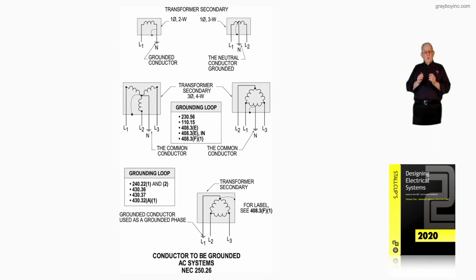I was very fortunate in one manner. In my electrical career, in the Metroplex area, you're going to see all these systems. The utility won't give you hardly any more at all delta. They'll give you a Y, and you'd have to set a delta transformer. They want everything balanced as good as possible back to them. So you'd have to check with utilities on that.